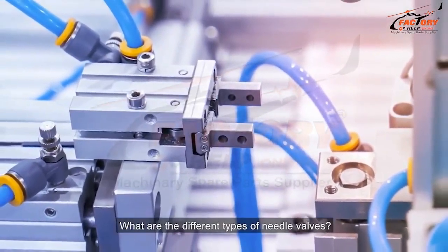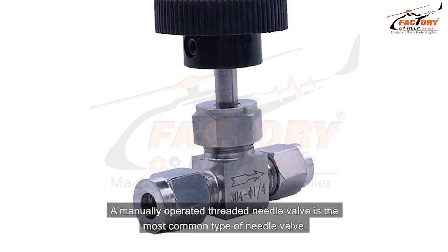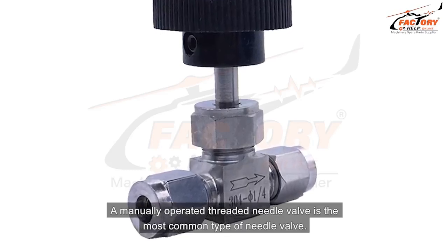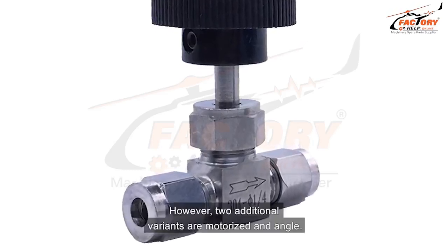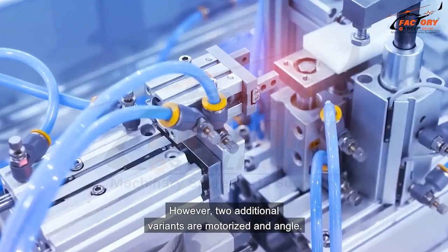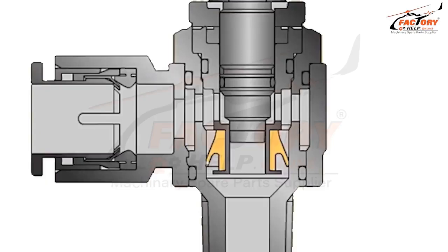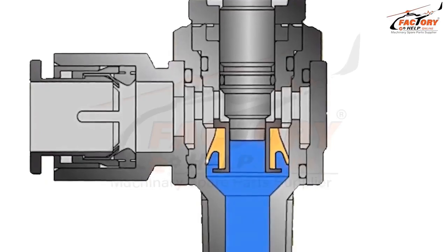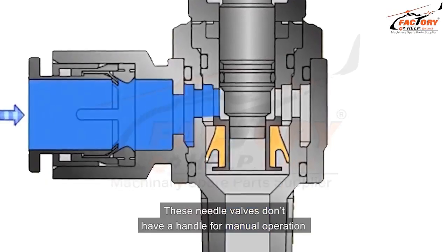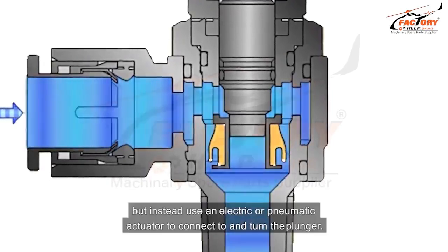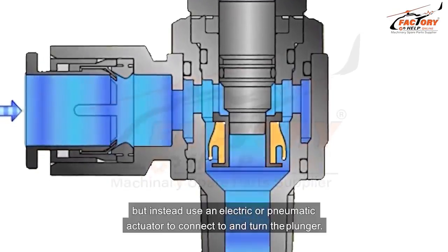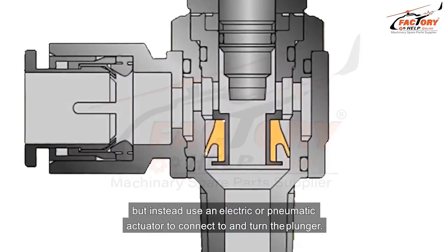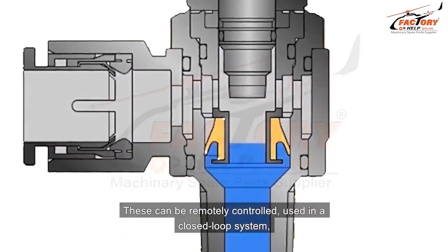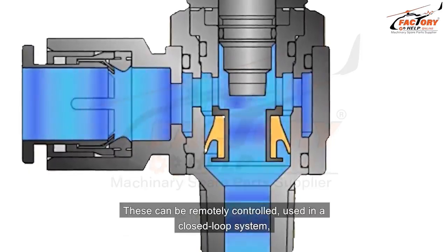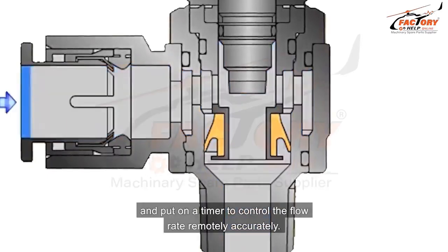What are the different types of needle valves? A manually operated threaded needle valve is the most common type of needle valve. However, two additional variants are motorized and angle. Motorized needle valve. These needle valves don't have a handle for manual operation, but instead use an electric or pneumatic actuator to connect to and turn the plunger. These can be remotely controlled, used in a closed-loop system, and put on a timer to control the flow rate remotely accurately.